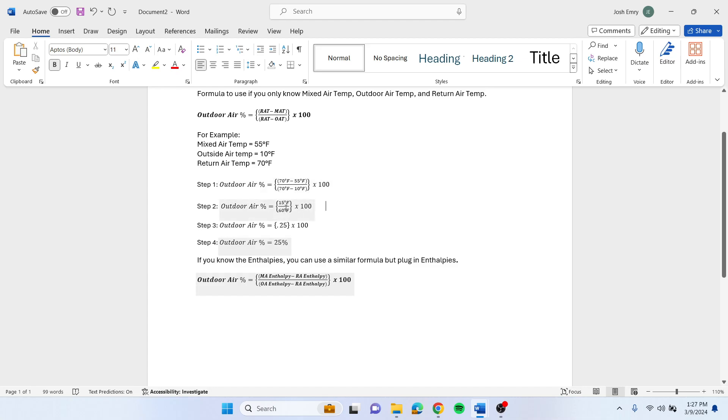You'll end up with 15 divided by 60, and then you take 0.25 times 100. Your actual outdoor air percentage is 25% with this information here.